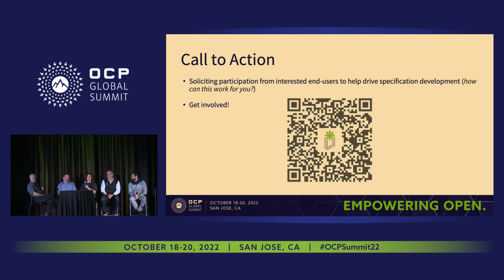Well, maybe I'll just comment on that real quickly. And yeah, I would love to talk at happy hour. We did look at that as an option. The efficiency of distributed heat is quite high, right? 80%, something like that. So you can transfer that quite easily. But converting it back into electricity is certainly a use case, but the efficiency was pretty low, like 7% at the high end for high heat. That was 70 C or above. So if you guys have higher, then really excited at lower temperatures to see this come to be, because that right there is the golden goose.